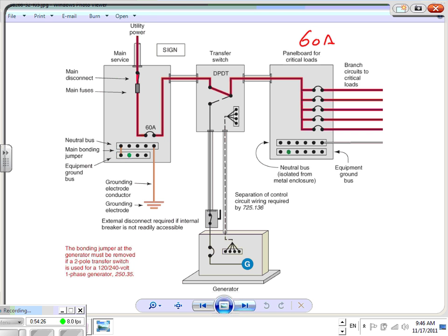And from the other side, I fit a generator. Now this can be a separately derived system or a non-separately derived system. Your choice. It depends on how you make it: are you going to switch the neutral? If I switch the neutral, this auto transfer switch will have 3 poles. It switches the hot, the other hot, and the neutral. If you switch the neutral, it becomes a non-separately derived system. If you don't switch the neutral, it becomes a non-separately derived system.